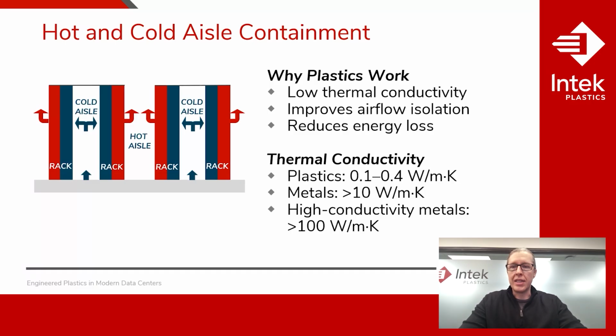Using ASTM D5930, we measure how heat moves through the material, often in-plane and through-plane, but plastics typically fall between 0.1 and 0.4 watts per meter Kelvin. Common metals, for reference, exceed 10 watts per meter Kelvin, and conductors like aluminum or copper exceed 100 watts per meter Kelvin. This massive difference makes plastics ideal for containment panels, louvers, ducts, and other structures that maintain strong separation between hot and cold aisles. Fillers can also play a role, raising or lowering conductivity depending on the formulation.